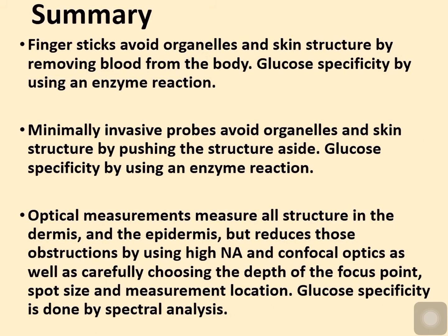It's brute force. You just slam that thing in there and the stuff gets wedged aside because they're tough enough not to tear. It does cause some damage to the area when that's done. And so when the probe is first put in, sometimes the measurements aren't quite right. And that's why companies like Abbott and Medtronic are working on those types of issues. And for glucose specificity, it does it just like finger prick. It has an enzyme coated on the platinum wire that reacts with the glucose and creates an electrical signal. And those last about 2 weeks before they have to be pulled out and removed.